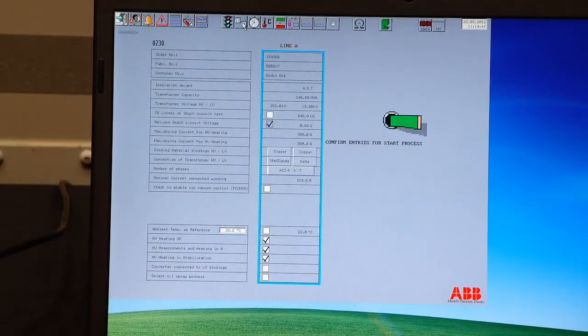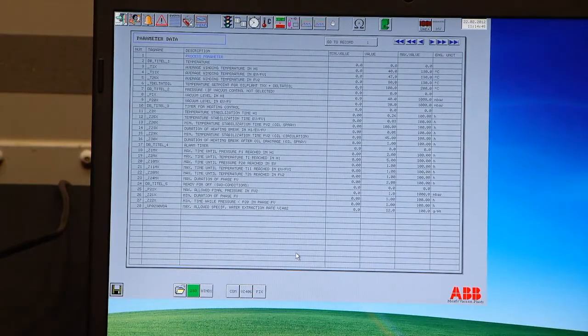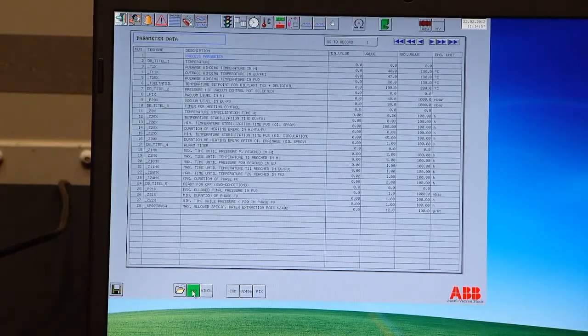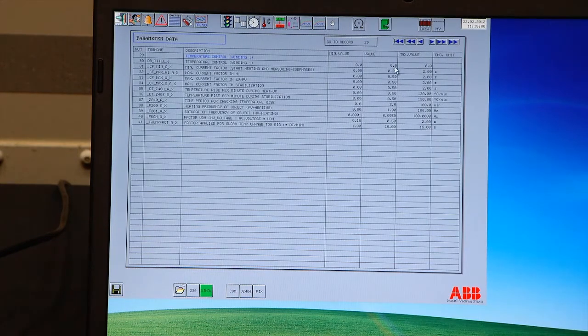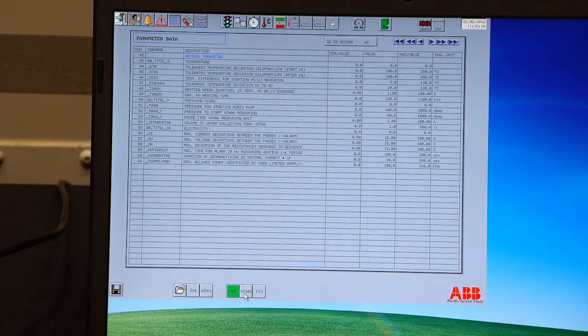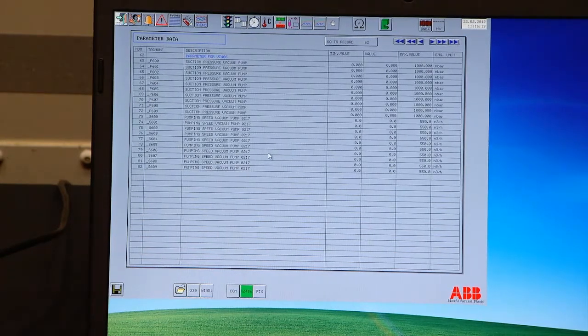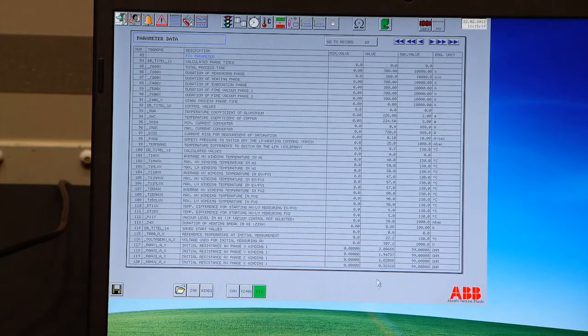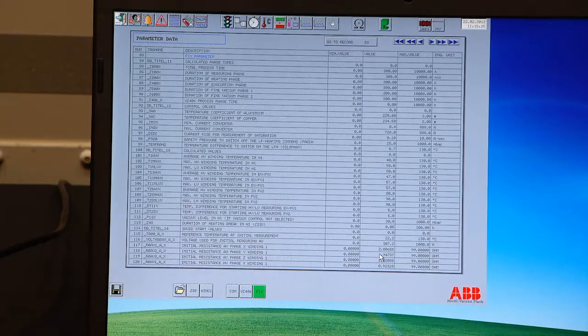We have a set of parameters. There are general ones which are controlling. That is up here next to the traffic light, between the traffic light and the watch. And in here there are 5 pages. There is a general one for the process, the specific one for the current control. There are common ones, and there are ones for the suction capacity measurement. That's the VZ406 connected to the vacuum pump stand. And there are fixed parameters which you cannot change. They are there for your information to see what is going on, what the limits are.